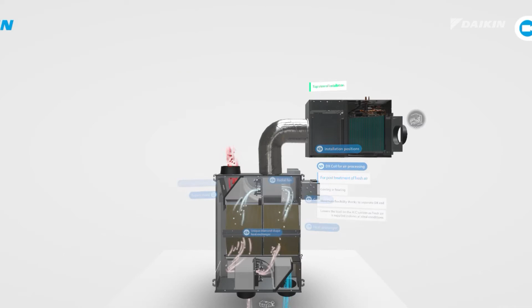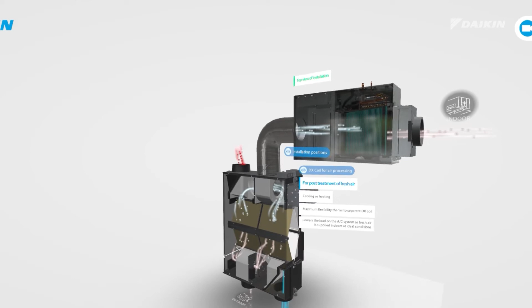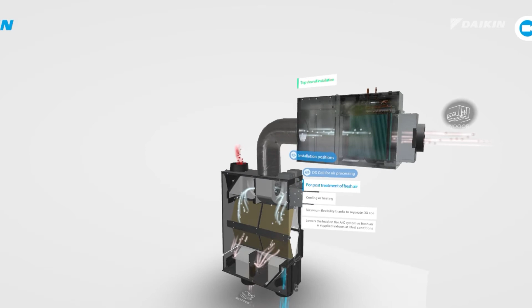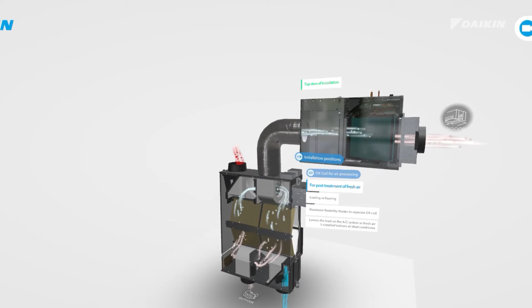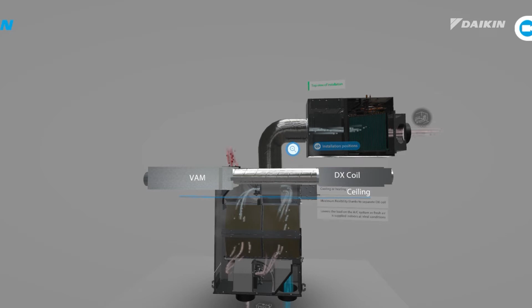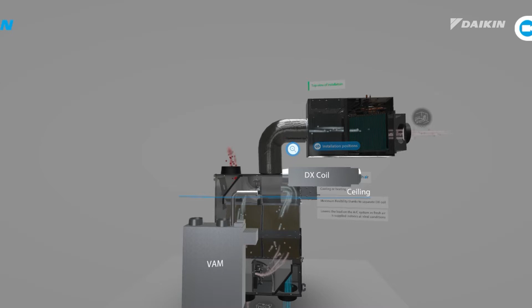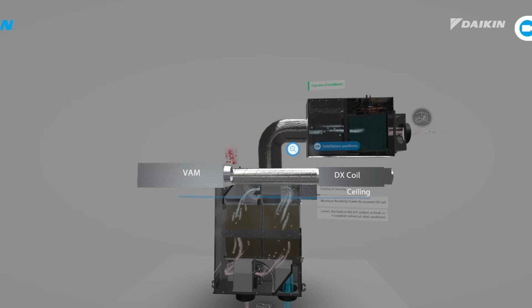For these cases, the use of EK-VDX-A is ideal. It is a DX coil module connectable to VAM via a field supply duct. This solution can either warm up or cool down the fresh air coming out of the VAM unit to a specific temperature, for airflows of 500 to 2,000 cubic meters per hour. This new solution offers great flexibility in installation, given that the VAM unit can be positioned horizontally, upside down, or vertically, and at different distances from EK-VDX.